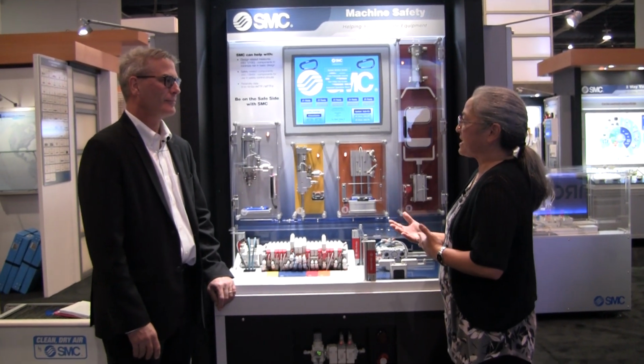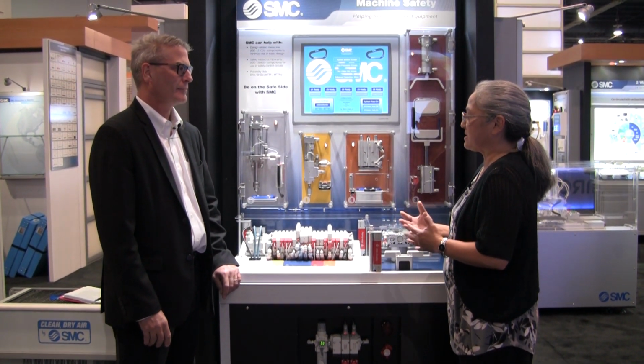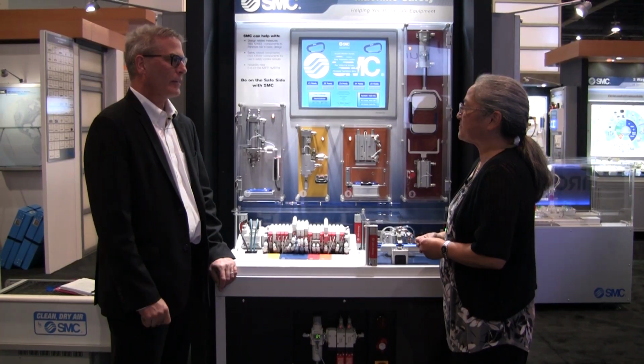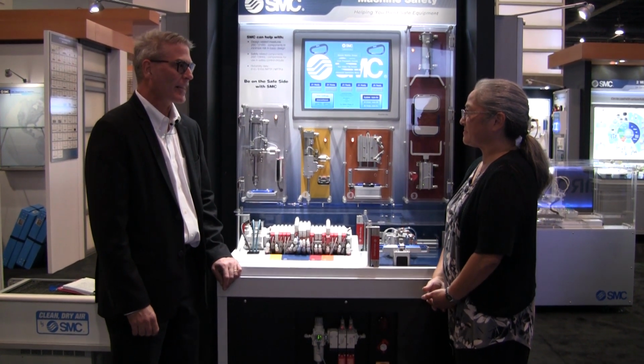So John, if I was a customer just learning about SMC and safety, where would I begin? Well, you would first of all start with the risk assessment, which means that you take a look at all of the hazards associated with the machine. Ideally, you try to design them out with an inherently safe design. And when you can't, you need to add some kind of controls to remove those hazards or reduce them to an acceptable level.